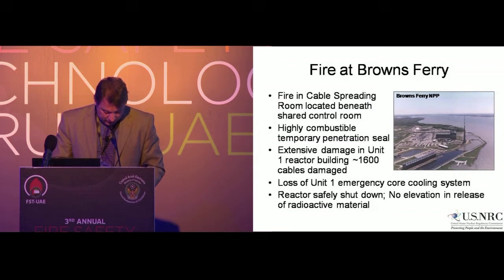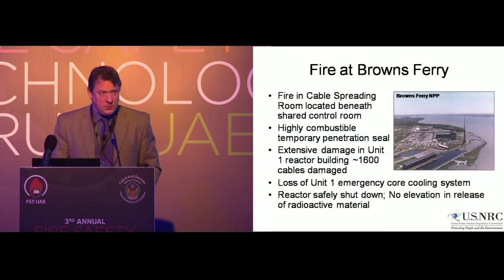In the cable spreading room, the extent of the burning was really limited, and the fire was controlled by a combination of the installed carbon dioxide extinguishing system and manual firefighting efforts. The major damage occurred in the Unit 1 reactor building adjacent to the cable spreading room, where there was a high concentration of electrical cables. Roughly 1,600 cables were damaged. The electrical cables, after the insulation had been burned off, had actually shorted together and grounded such that control power was lost for much of the installed equipment. The reactor was safely shut down, but the emergency core cooling system for Unit 1 was rendered inoperable. So this fire affected both trains of safety system.